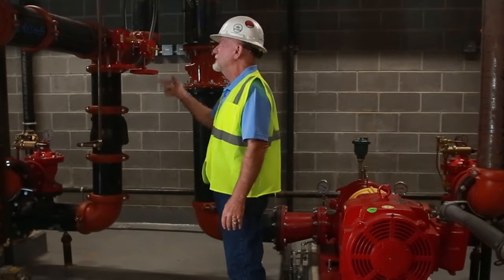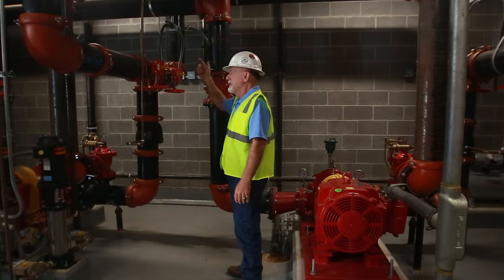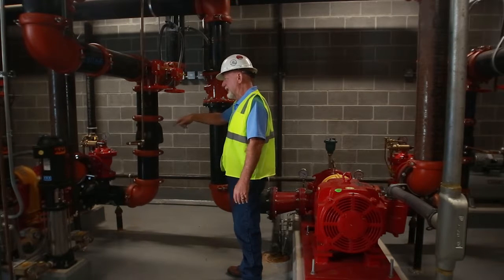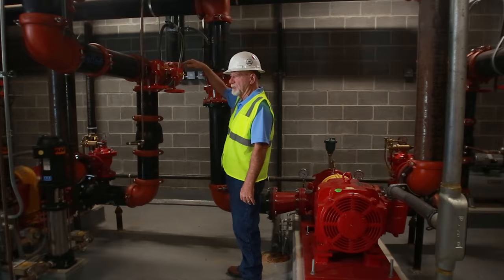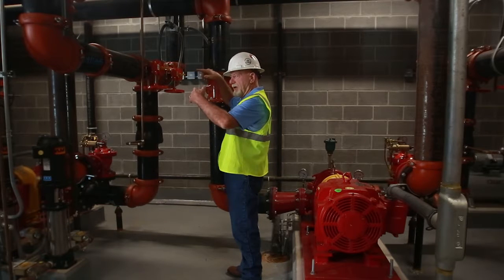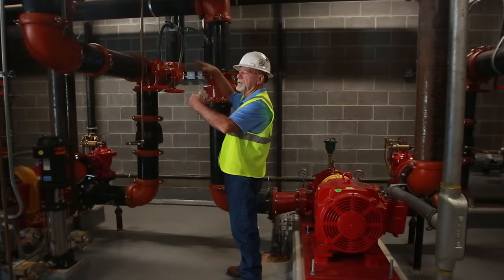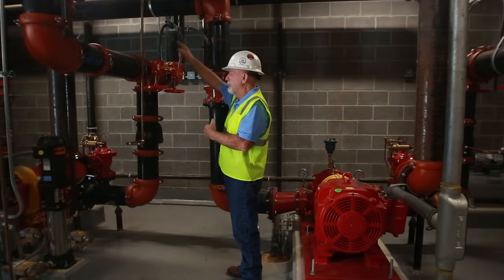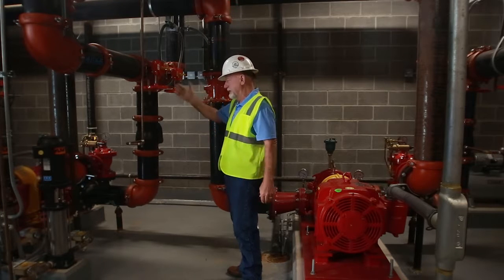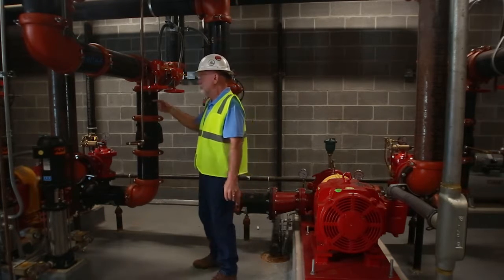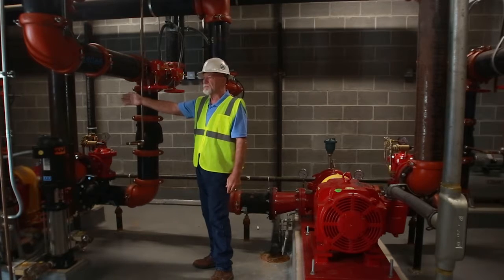Typically, when we see one set up with a flow meter like this, the water, once it comes out of the pump head and goes into the major piping, if there's not a fire and you're wanting to do a test, you've isolated the system, and then that water is recirculating back in. But the design engineer did this one so that it dumps to the outside.